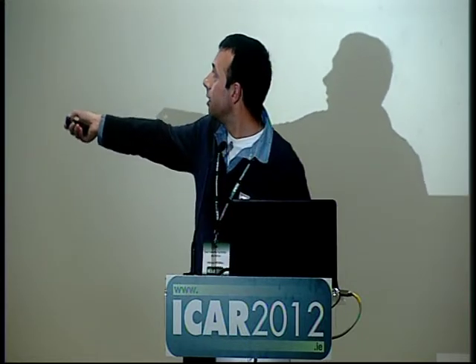In terms of bias, it's actually the same. The bias becomes 0 at the end, which is logical. But before, you can see which samples are the most different, of course the Bentley, because they are the most different from the FOSS instrument, which is the master, and also the Delta, okay?